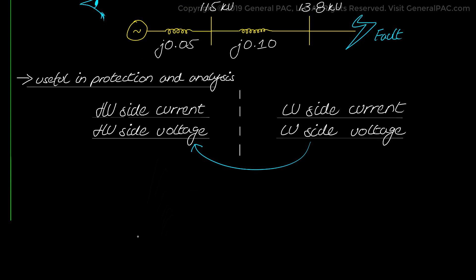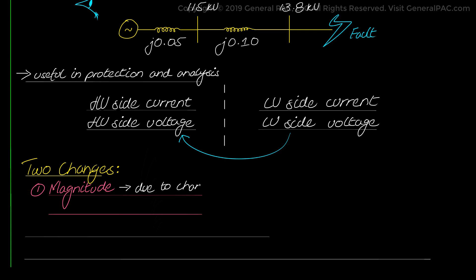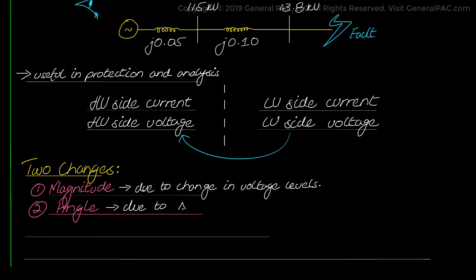To do this we have to account for two changes in sequence current values. The first involves the magnitude due to the change in voltage level, and the second involves the angle, since we have a delta-y transformer and the angle will be subject to change.